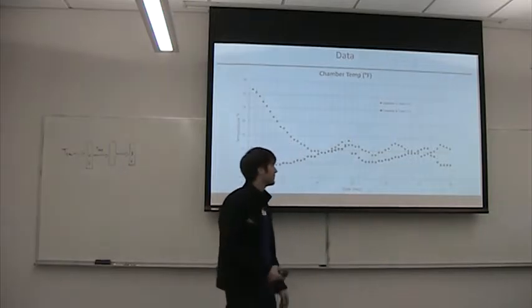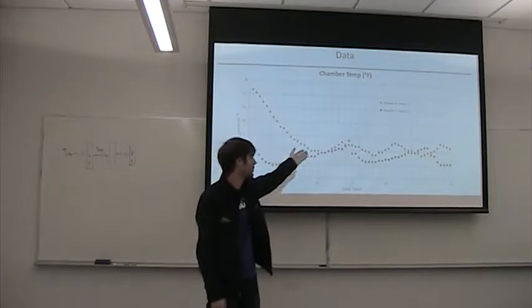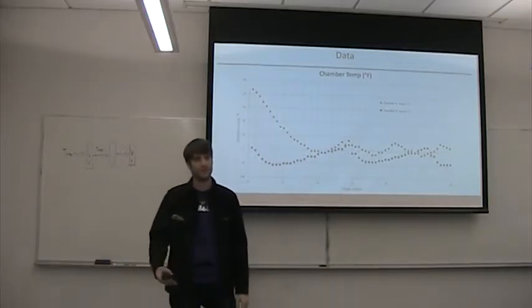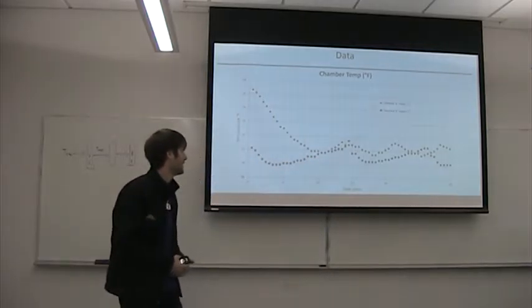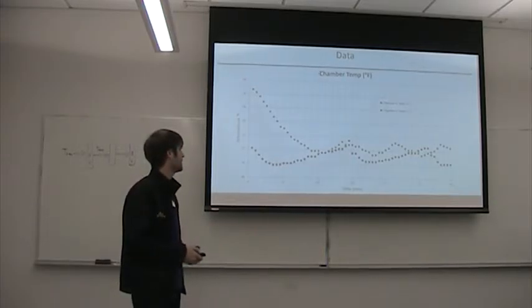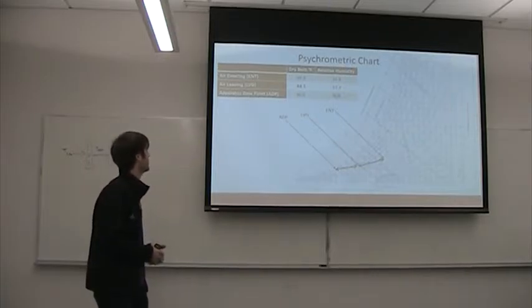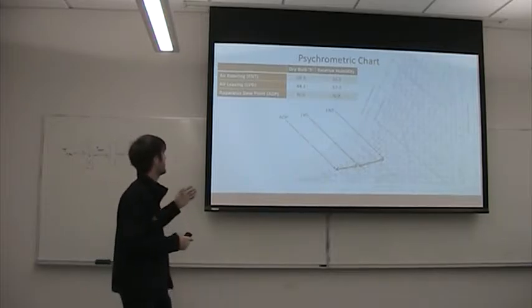And so this is the plotted data of the temperature of the room over time. So initially it started off fairly warm and then as we cooled down. Chamber A is the room with single-pane glass. So you can see where the valve cooled the room off, it heated up, cooled the room off, it heated up almost cyclically.